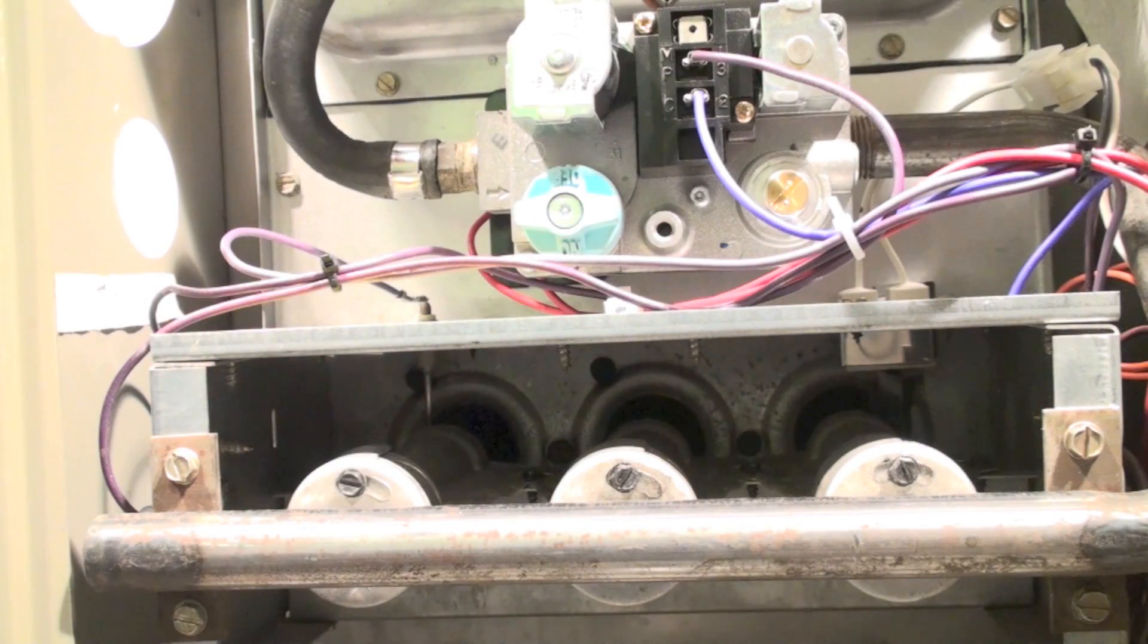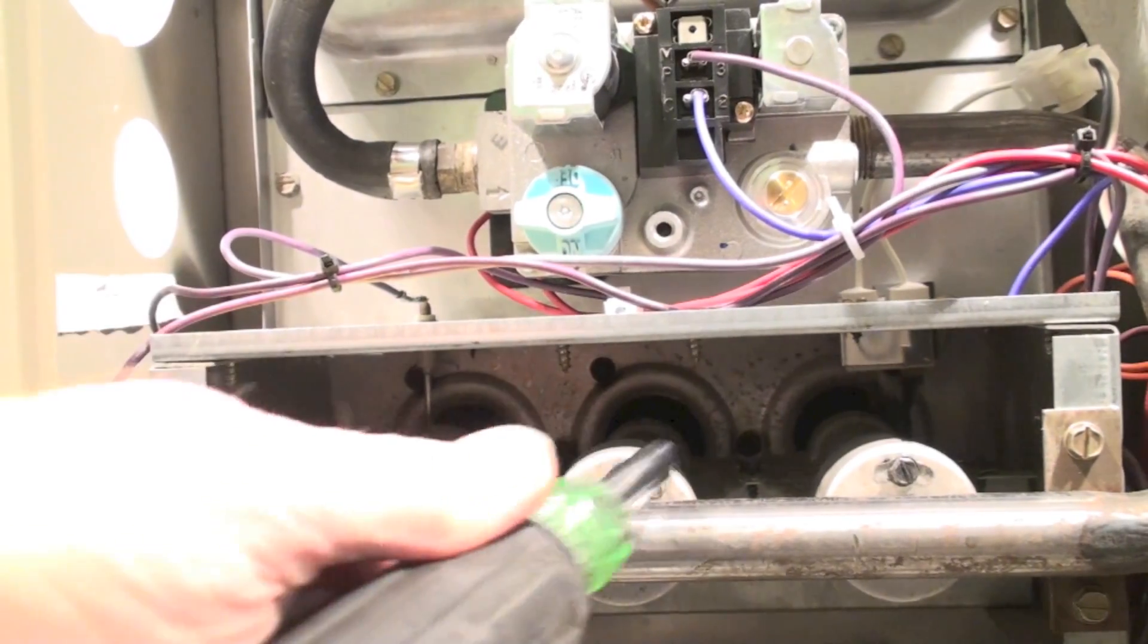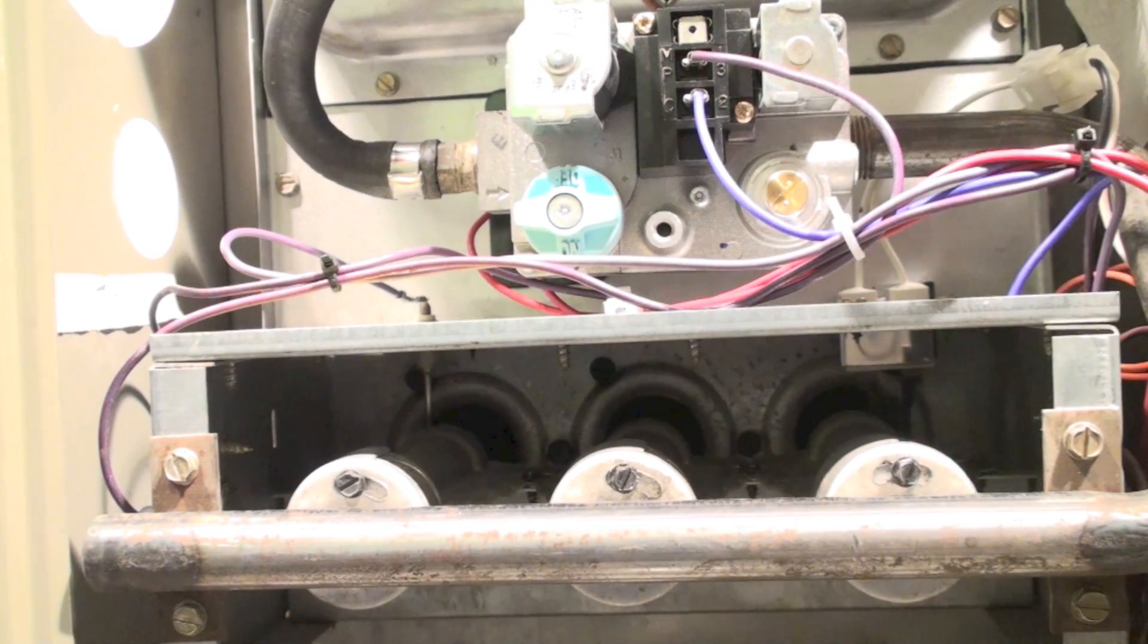Okay, once we have the firing rate correctly set, we're going to adjust the burners. Now most new furnaces do not have adjustments on their burners anymore - they've taken that out - but this one does. It's kind of hard to tell on these in-shot burners when they're burning right. What we'd like to do is get rid of the yellow tips.